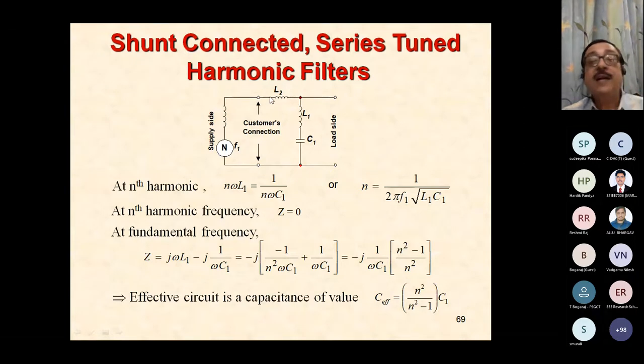And I have a distorted current at the input side. Now the current is actually not because of my load, but because of the so-called import of harmonics from external sources. It creates a lot of problems, not only in terms of harmonic losses at the input, it also creates problems in terms of overloading of these filters, because they will be designed for a particular magnitude of harmonic current. If additional harmonic current is coming in, the current capacity has to be enhanced. So what we do is we put a series choke here, which is also called the detuning choke, so that if the current tries to flow into my premises, it will see a reactance proportional to n times L2, so that it will not be very easy for all those harmonic currents to flow into my premises. So this is more of a detuning choke rather than a part of the filter.